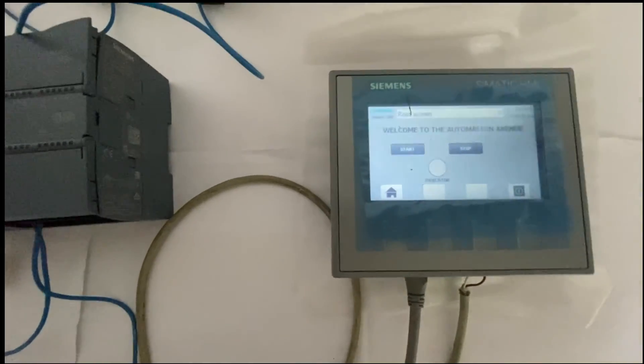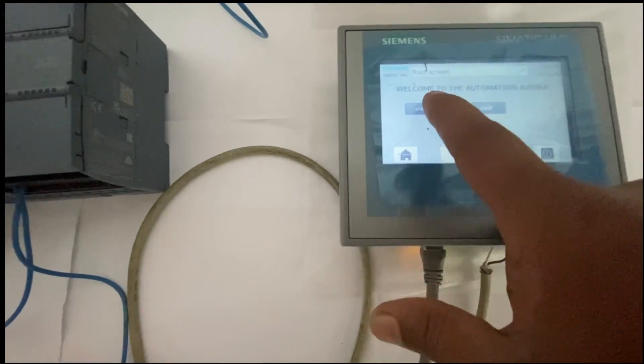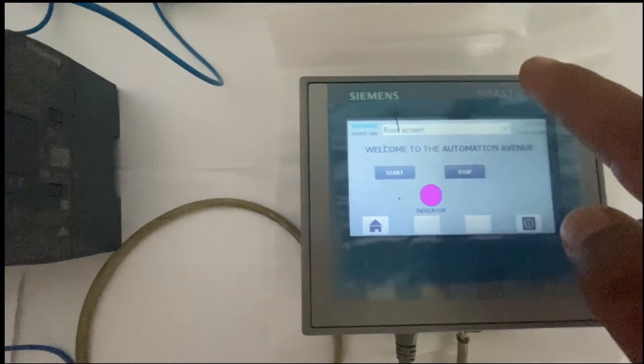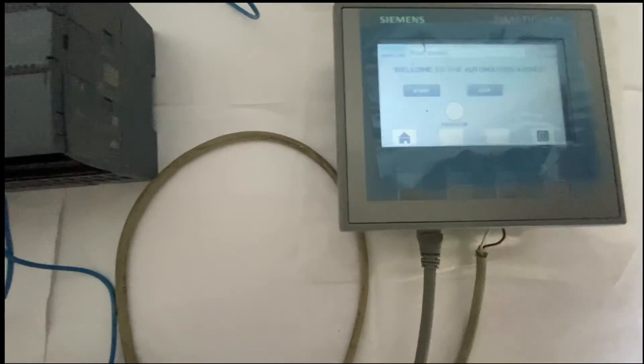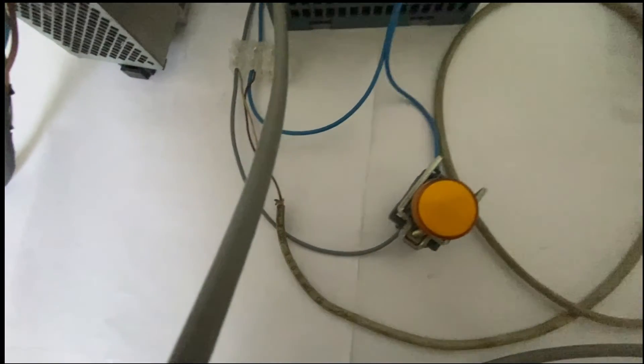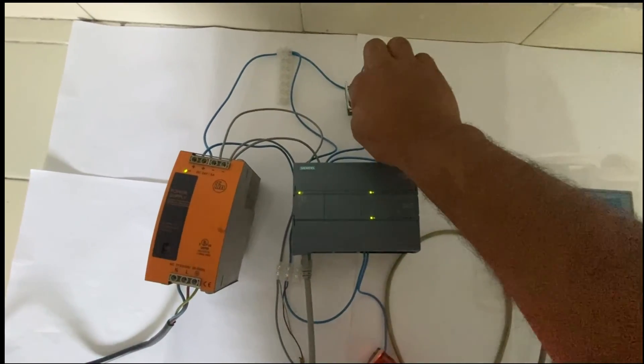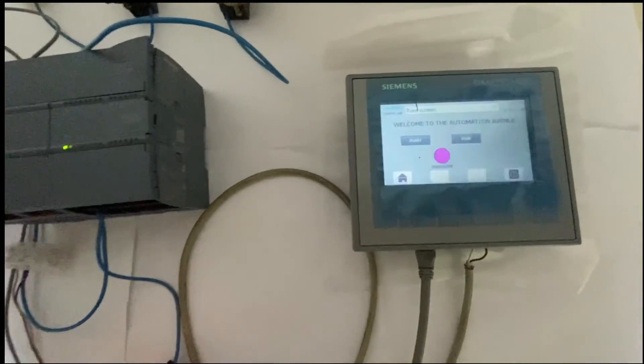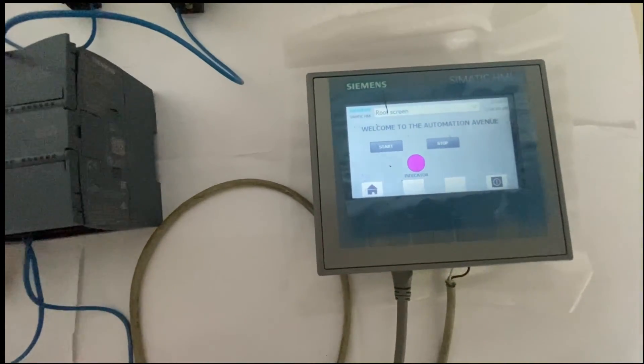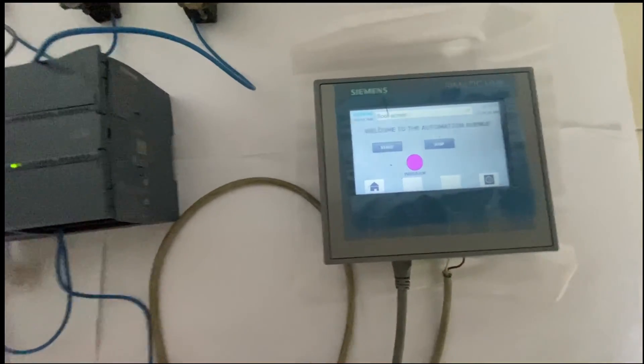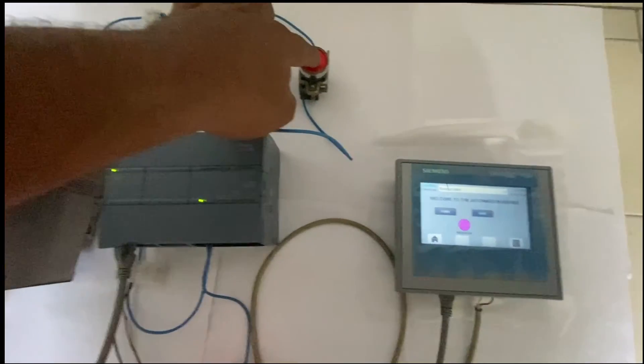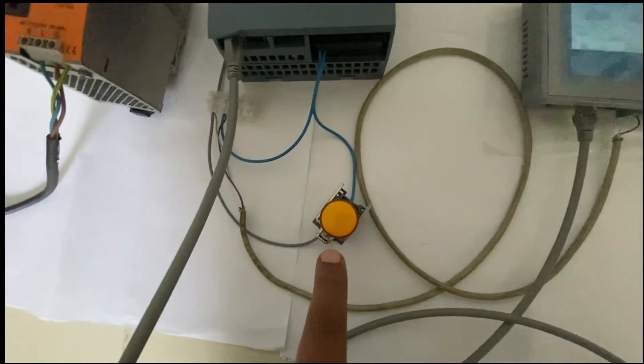Click the Start button on the HMI — you can see the indicator turns on and the light is on. Press the Stop button — the indicator stops and the light turns off. We can also start by pressing the physical start button — the light turns on and the HMI indicator also turns on. We can stop from either the physical button or the HMI Stop button — the indicator stops and the light turns off.